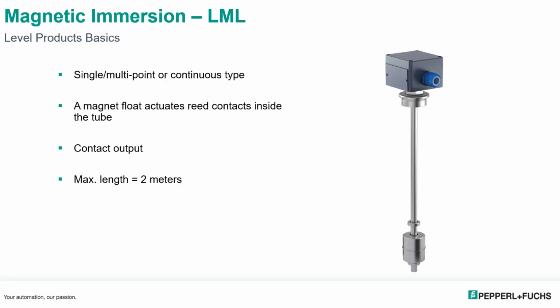The next point level control we have is the magnetic immersion probes, which are the LMLs. You can get this in single or multi-point. Now this probe has a reed switch inside. For multi-points, we just put the reed switches at different heights where you want to detect the medium. It's a magnetic float, so as it moves up and down the rod, it activates the reed switches. Maximum length is about 2 meters, and that's really about shipping purposes too. So about 2 meters is the max.